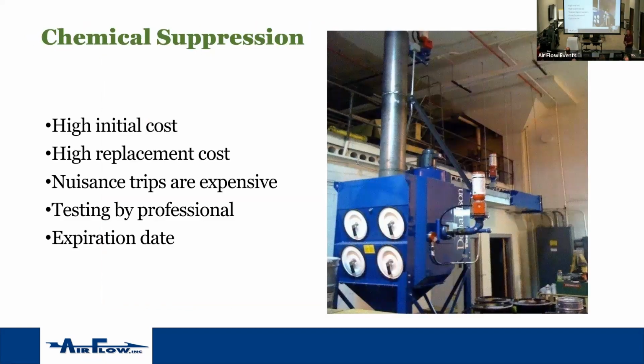A lot of that gets set up during startup, because you'll have how long that valve needs to stay open for to extinguish the dust itself. But the more important thing is on the install side, that distance between the photo eyes, your Grecon spark sensors, and where your valve is calculated by the feet per minute going through your duct. So you'll need to know how fast, what's your conveyance speed, what are you picking up through your ductwork in your feet per minute, that velocity. And that velocity itself is what's going to dictate how long it takes for the signal to get from that sensor to the control panel, from the control panel to the valve, from the valve to open up. So it's picking that spark up, and it gives it a good plus or minus as that spark comes through to extinguish it. So that's a calculation.